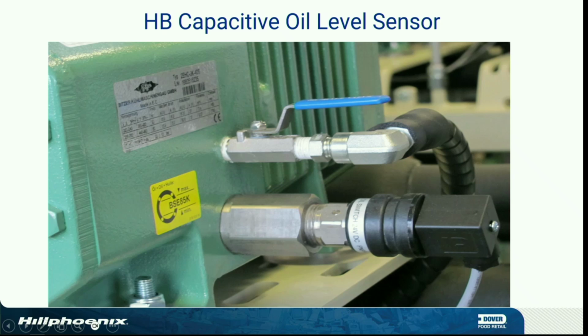Some of our older racks, and we started in June of 2019 was the first rack we shipped with an OMC oil module on it. Before that, we had our HB sensors on our compressors. These are the exact same switches that are in the separator and the reservoir. Anybody working on any of our older racks? The gentleman right up there was. They had a pulse width modulation combiner up in the flex combiner, right? That runs those things for medium temp. They're on 30, off 30. So it's a 1-minute cycle, and then your low temp was 5 seconds for 55 seconds, right?